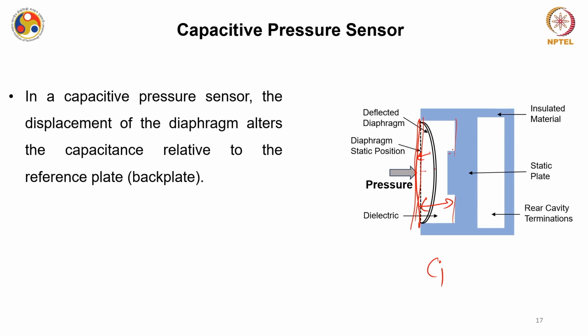Note that this area bulges out because it's the pressure-sensitive region. Since this is a single piece of silicon, the edges are hinged, but the central plate deflects. As the central plate deflects, both the permittivity epsilon and the gap d change in between. So now you have another capacitance, the final capacitance CF. Using these two capacitances, you can derive an equation for pressure, which is mostly nonlinear in nature.